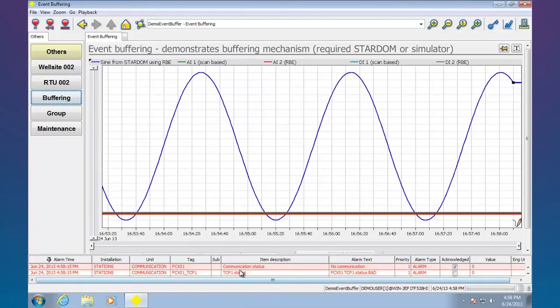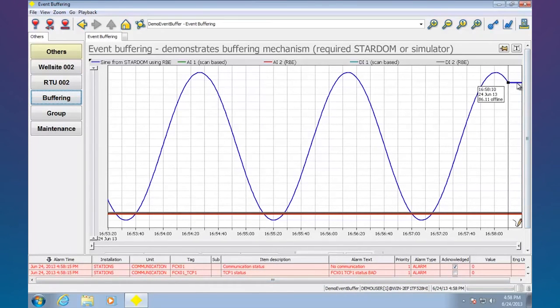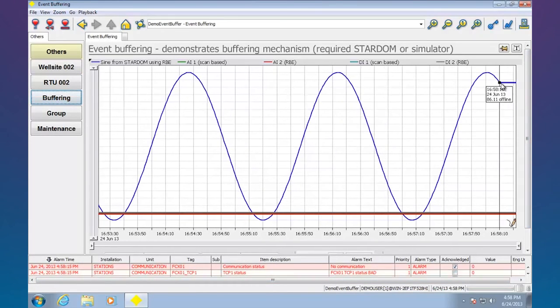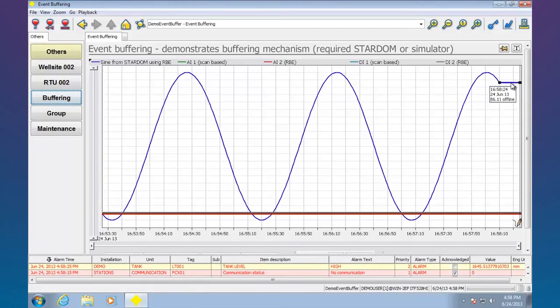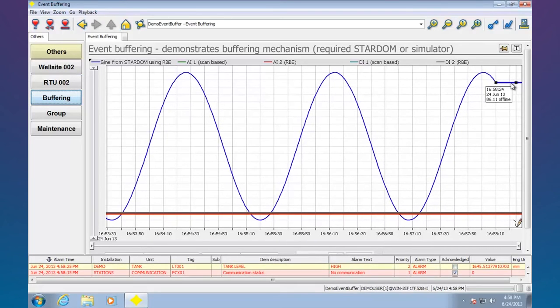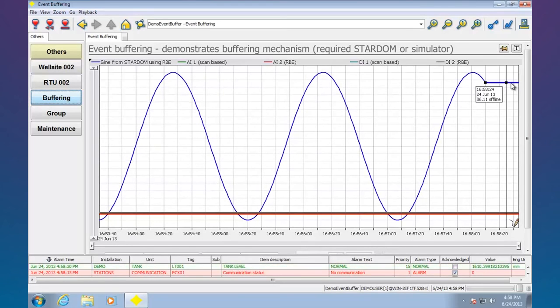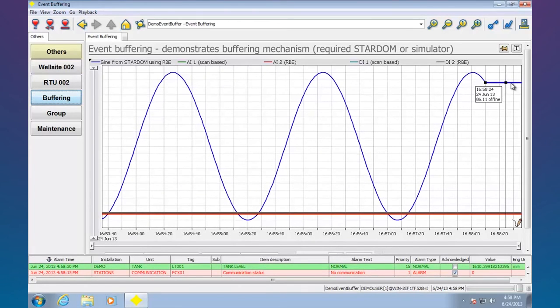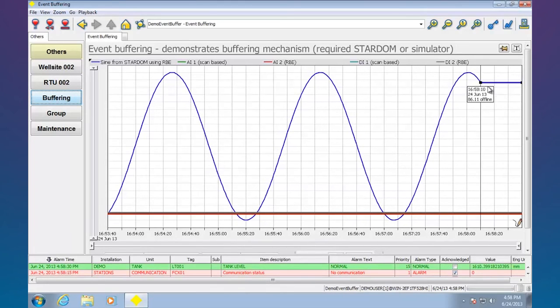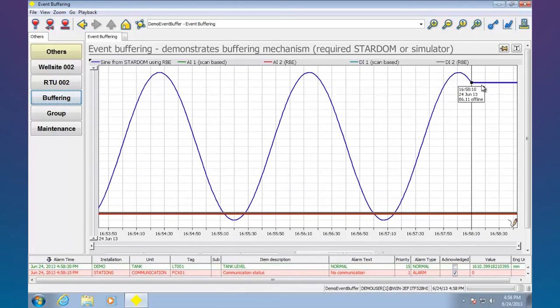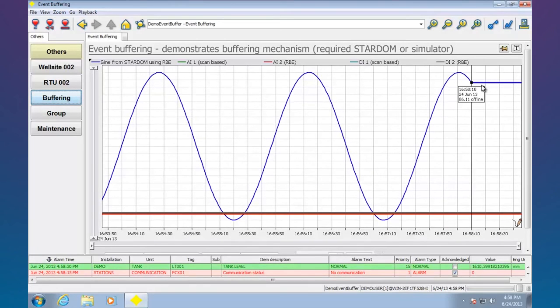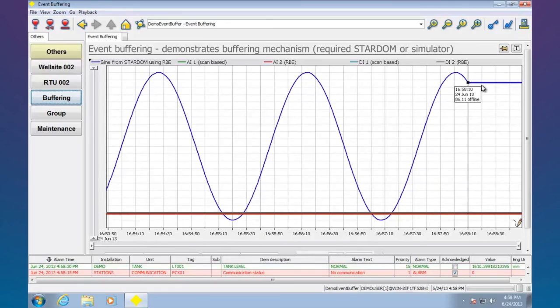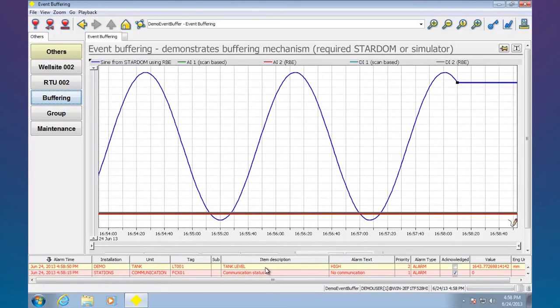What I'm going to do right now is I'm going to simulate a network disconnection by actually going to the controller and disconnecting the ethernet cable. We can see right now at the bottom, my communication status went bad. We can see on the trend that essentially these samples of data I was hoping to get, I'm no longer getting them. It's offline. I'm going to reconnect the network to that controller. What we should see after a few seconds is the communication status is going to go good, and then we'll actually see the trend get rebuilt. That's just an example of not losing any data, the buffering capability of our products when combined here. In a couple seconds we should see this trend get rebuilt.